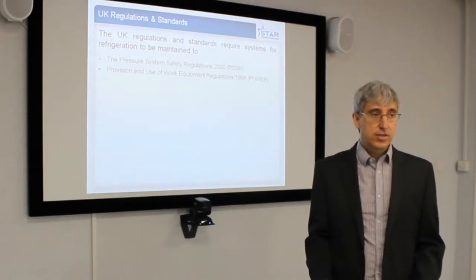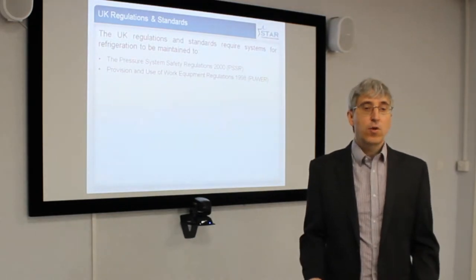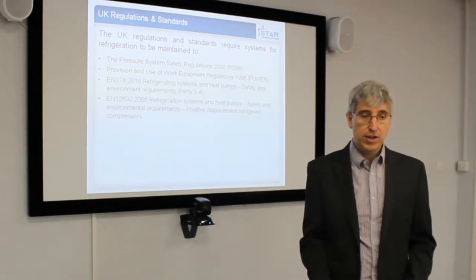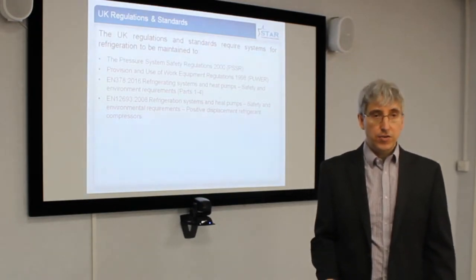The UK regulation standards appropriate to ammonia refrigeration systems — there are a lot of them — but the Pressure System Safety Regulations 2000 and the Provision of Work Equipment Regulations 1998 are the most applicable regulations, while the most applicable standards are EN 378 and EN 12693.